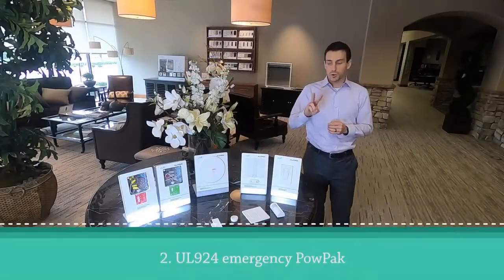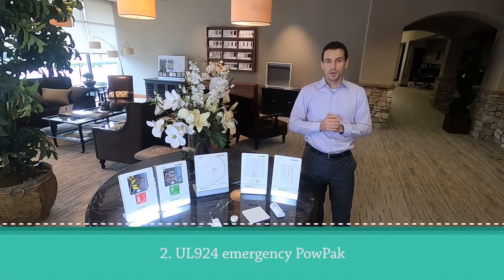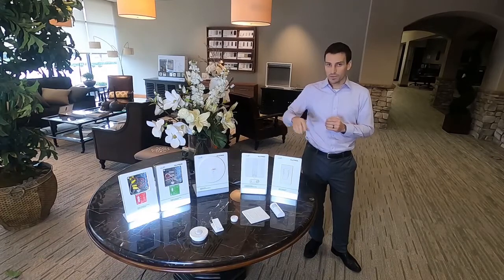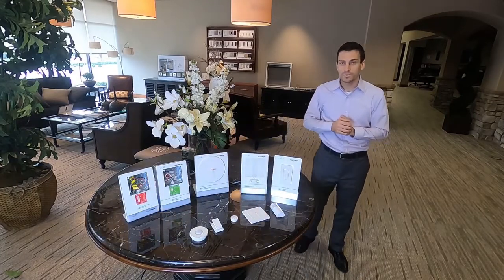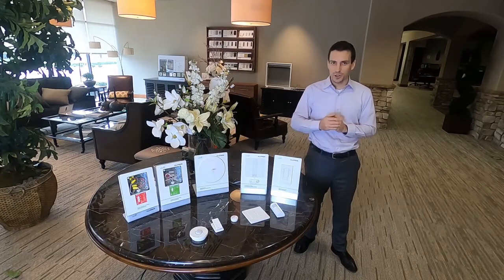Emergency lighting solution number two is the red UL924 emergency PowPak. By building software intelligence into the PowPak itself, we've alleviated the need for emergency bypass relays. During normal operation, the red PowPak operates just like a green PowPak — so for example, this Pico remote is programmed to turn them both off. But when utility power is lost, it operates a little differently. Let me show you.